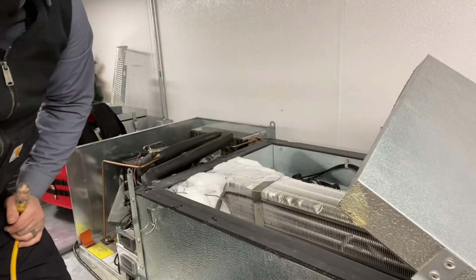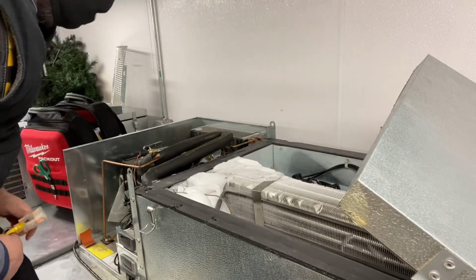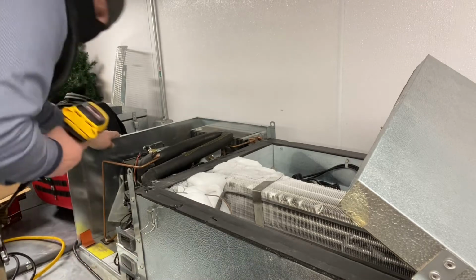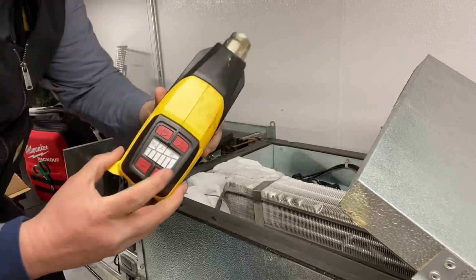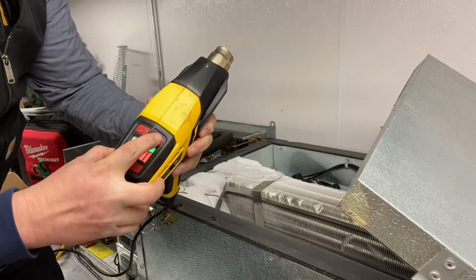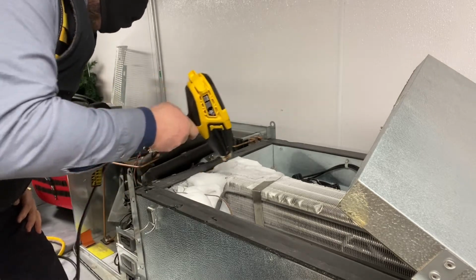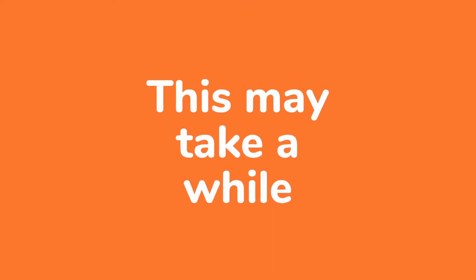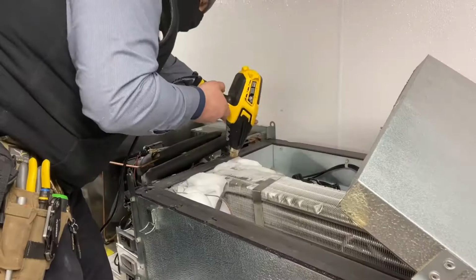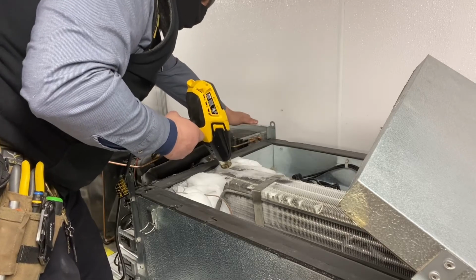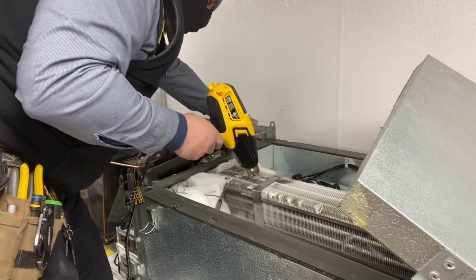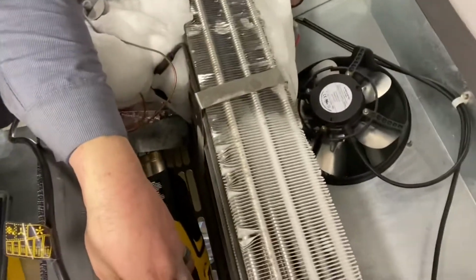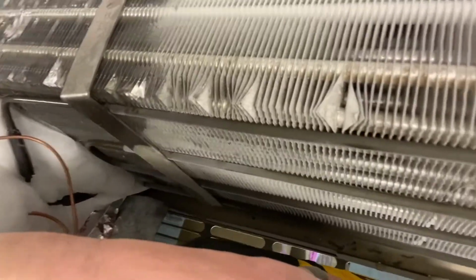For defrosting this freezer, I have almost like a hairdryer. Now this hairdryer can get really hot. You'll see that where we are still freezing is right where the defrost heaters are not on the coil. So you can see that where it's not on the coil is where we're getting most of our problems.